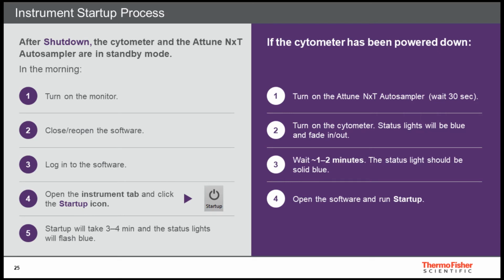In case of a complete power cycling of the instrument, the correct sequence is to turn on the autosampler first, wait for 30 seconds for the autosampler to complete initialization, that is essentially the tray stops moving. Power on the Attune NxT from the switch in the back. Wait for the lights to stop blinking blue. Blinking blue is a state in which the firmware is being uploaded. After the lights are solid blue, go to the instrument ribbon on the software, click on startup, and follow the directions seen on the software.